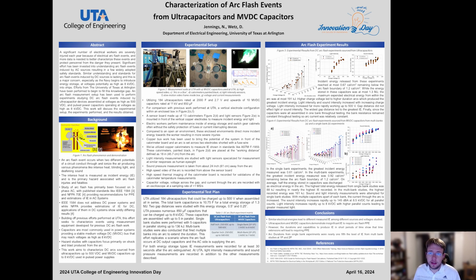The highest total electrical energy dissipated inside a single bank experiment arc was 88 kilojoules, resulting in the highest incident energy recorded. In the multi-bank studies, the highest recorded energy dissipated into the arc was 161 kilojoules, which only resulted in 0.3 cal per centimeter squared release.